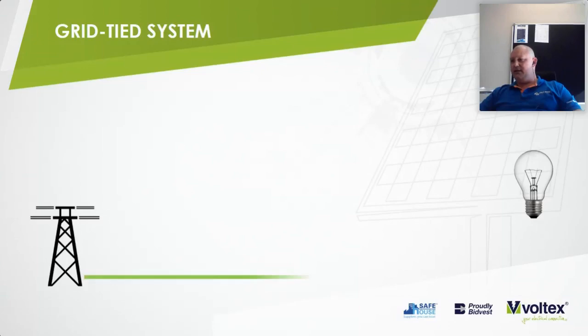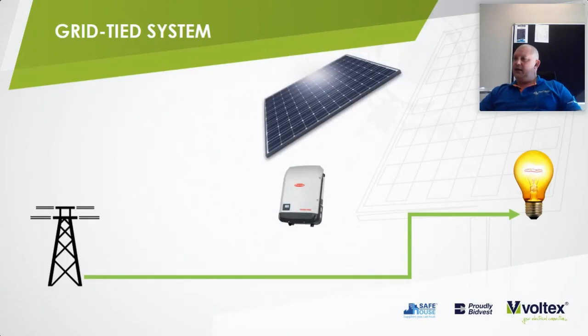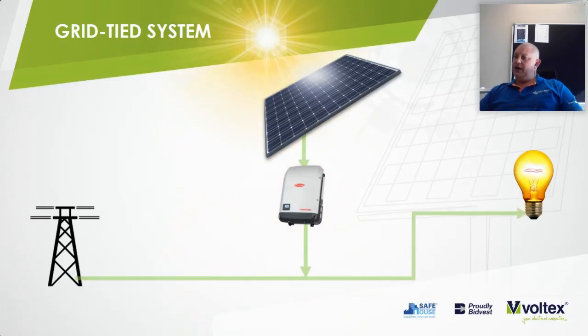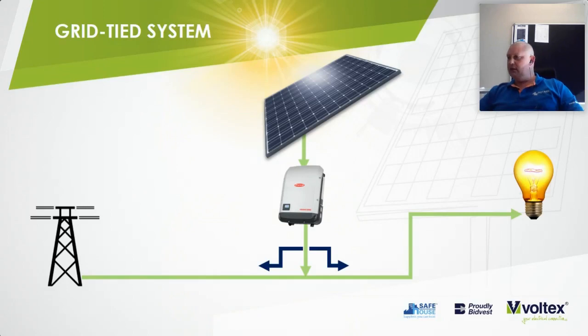So similar setup, you've got your AC line powering your loads. By adding a grid-tied system to the equation, you can feed power into that line. Now, in areas where you are allowed to export, you can export the power back for zero metering or for a rebate. In the event that you're not allowed to, and this is a preferred system specifically for domestic purposes and areas where you're not allowed to feed back, we add an energy meter to the equation on your main incomer.